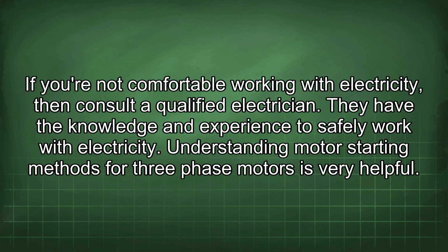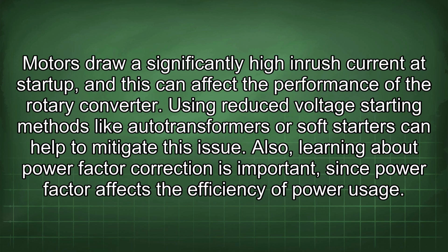Understanding motor starting methods for three-phase motors is very helpful. Motors draw significantly high inrush current at startup, and this can affect the performance of the rotary converter. Using reduced voltage starting methods like auto transformers or soft starters can help mitigate this issue.